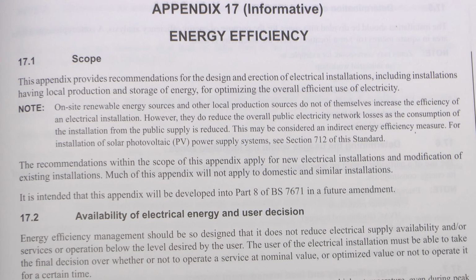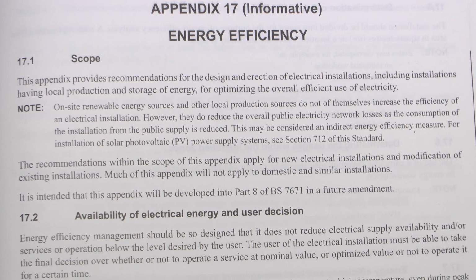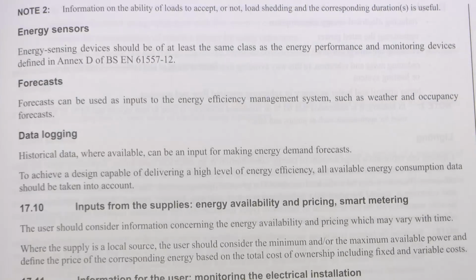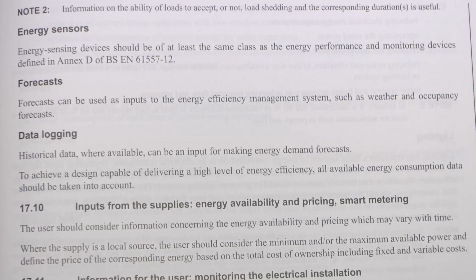Most of what this concerns is things such as voltage drop, making sure it's at a low level, making sure the actual cross-sectional area of conductors is a suitable size but compared to not wasting energy by heating the cables, power factor correction, and various other items as well.